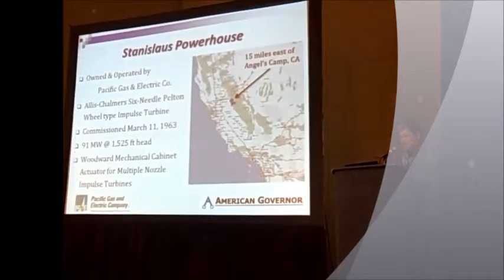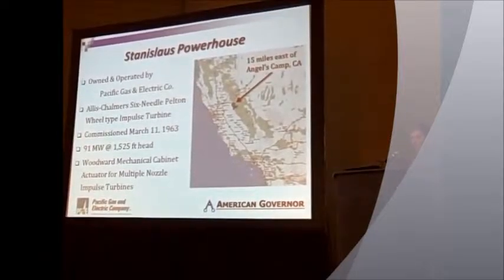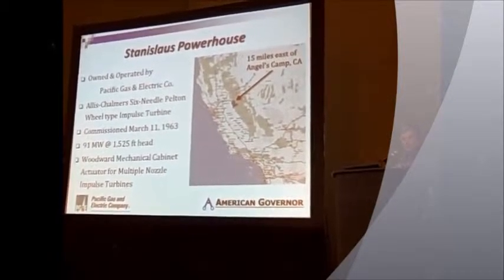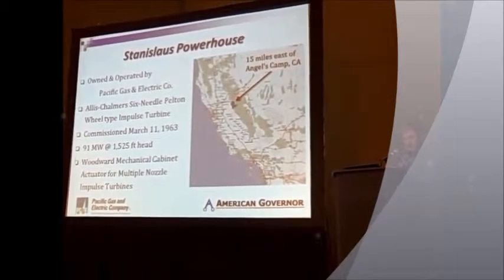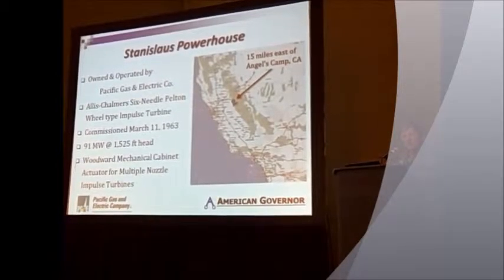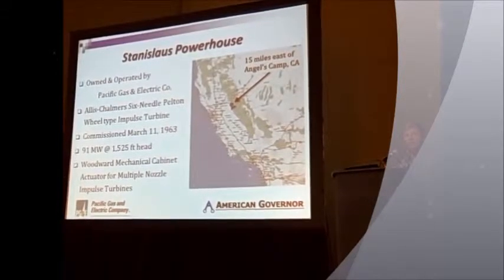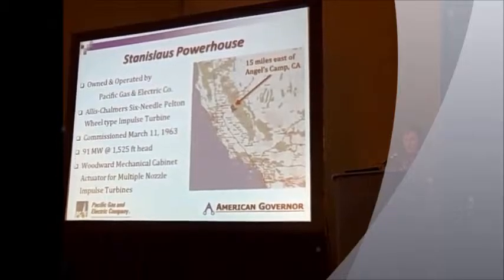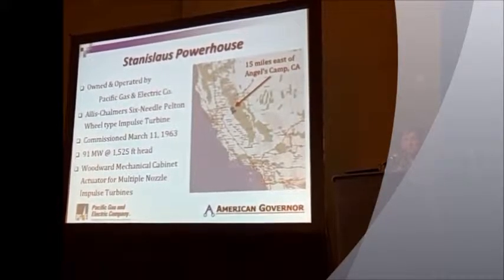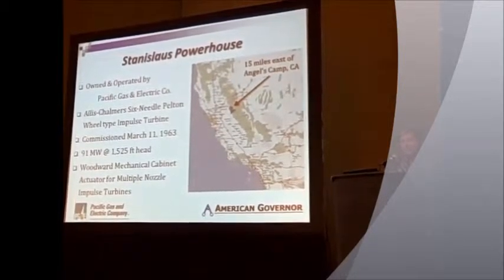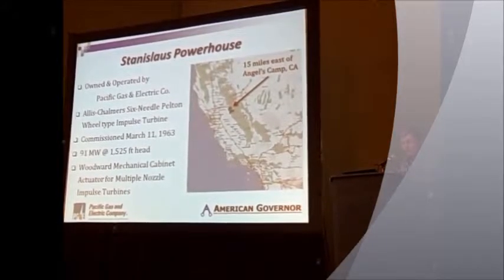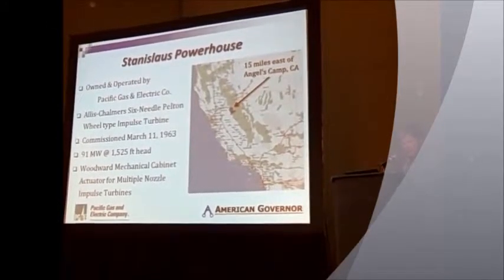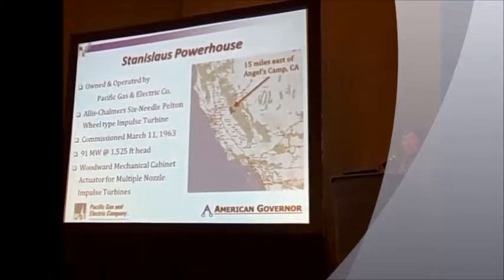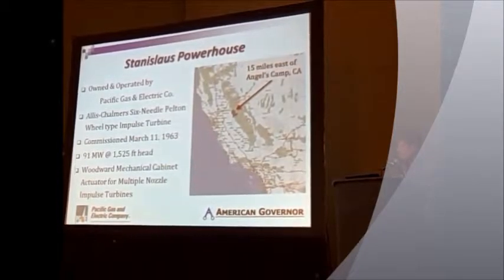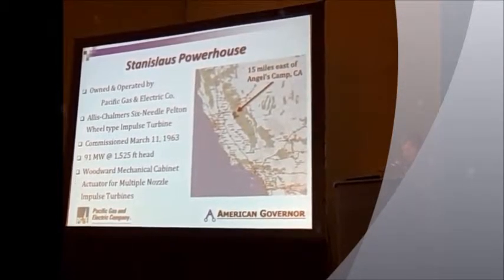But Stanislaus is a 91 megawatt, 6 needle jet vertical unit. It's capable of about 800 CFS. The water supply for this unit is around 550 CFS, so this unit is used for ISO control and is moved all over the place. It's actually one of the largest single unit plants in the PG&E hydro network.